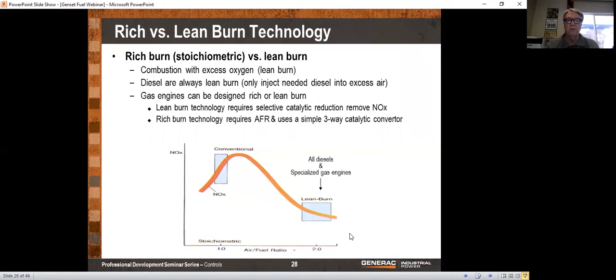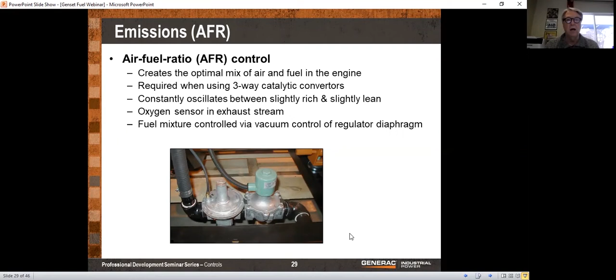We represent Generac, and they say that all of their natural gas and diesel engines can be guaranteed to start two of them in parallel within 10 seconds. That's because we're using rich burn technology — rich burn means you have more fuel than air, while lean burn means more air than fuel. But we also use an air-fuel ratio controller so that after they start, we go to stoichiometric, meaning there's not an excess of fuel or air — we run both in balance.